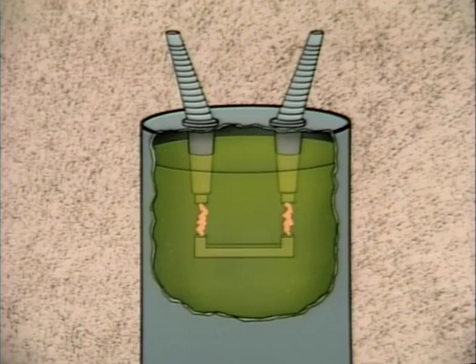When you're using switching devices to de-energize a circuit, it's absolutely critical that you know which devices can be operated under load and which ones can't. Most circuit breakers are designed to be opened under load because de-energizing circuits is one of the basic functions of a breaker. With disconnect switches, this is not always the case.